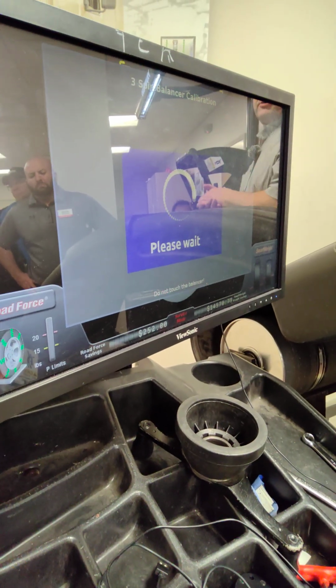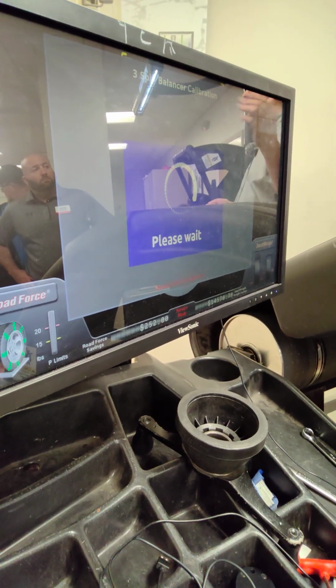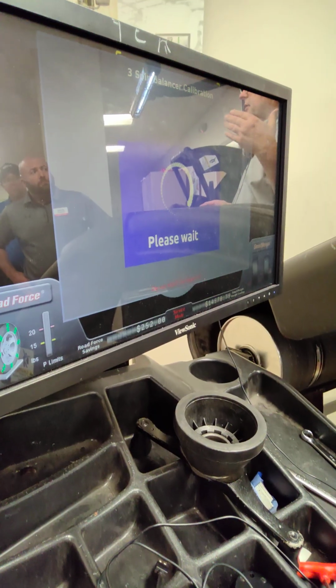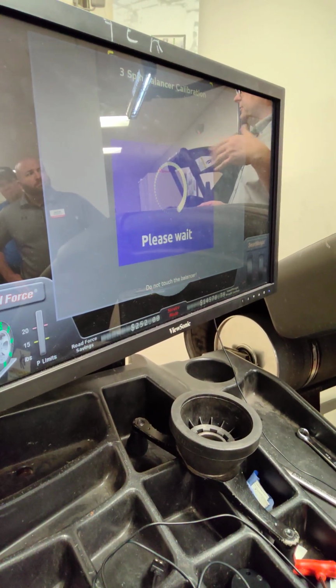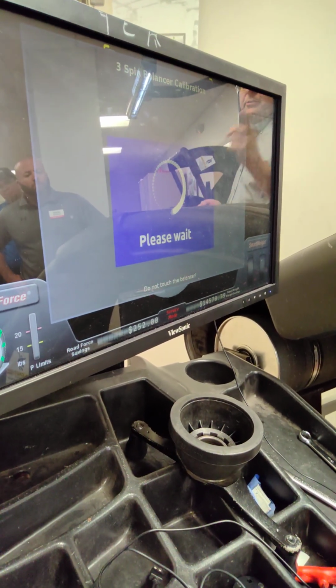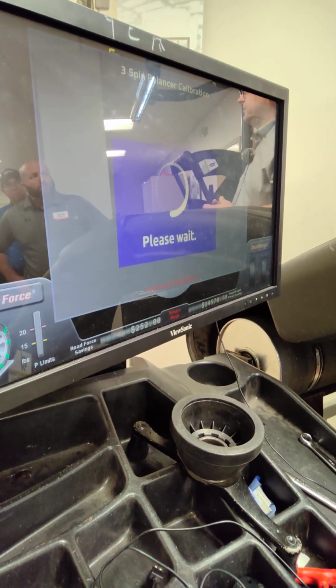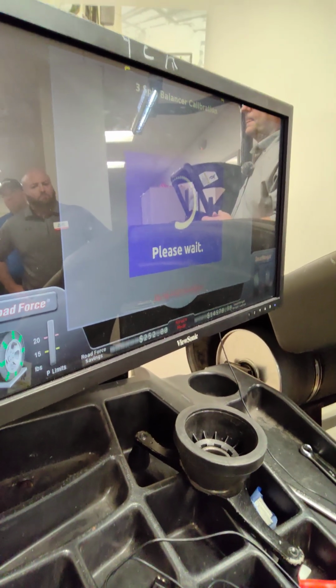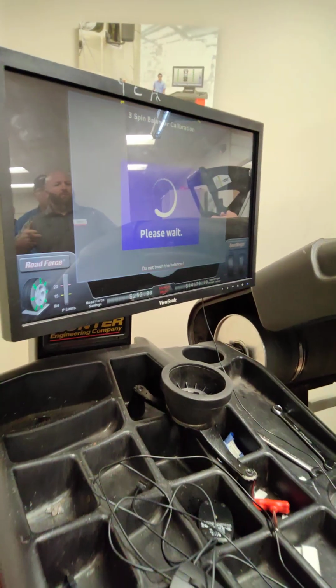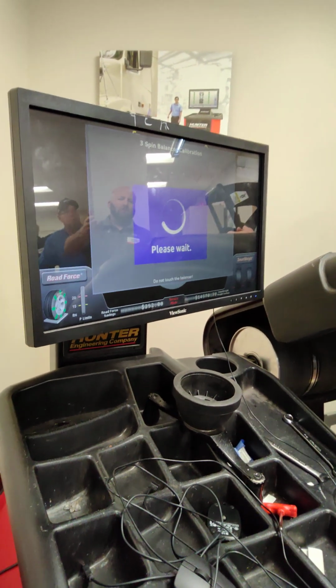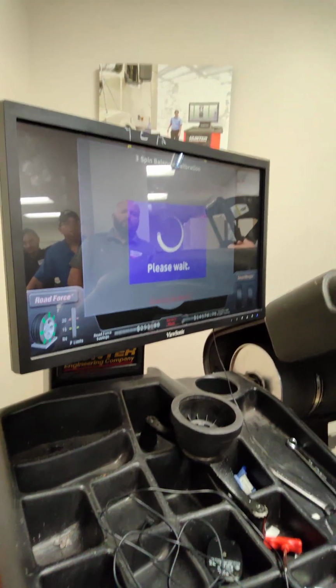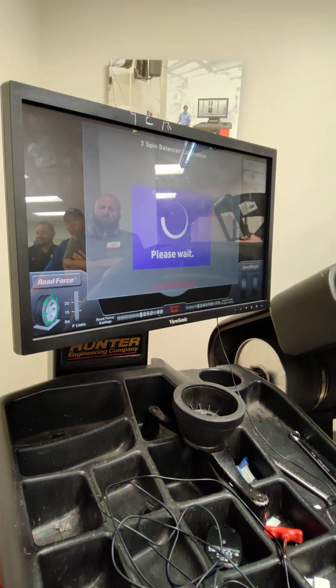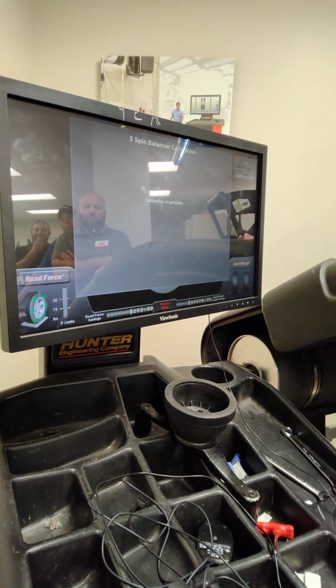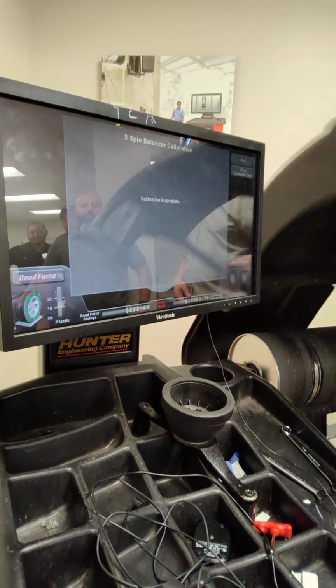So we're going to recalibrate it again, and this time we're going to hit the quick calibration check right after we do the 3-spin cal. The other thing that bothered me is you said this took a long time to do. It did. Yeah, it took because we hit ours at the same time. Ours is newer, but it took like 2 minutes longer than this one did. Okay, so that was a lot quicker. That's an acceptable amount of time.